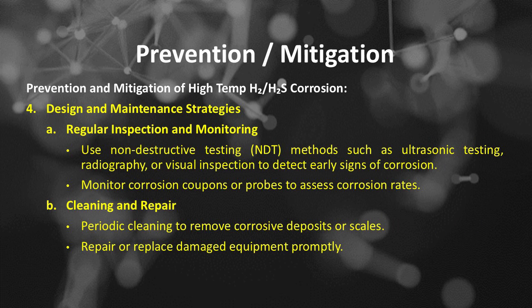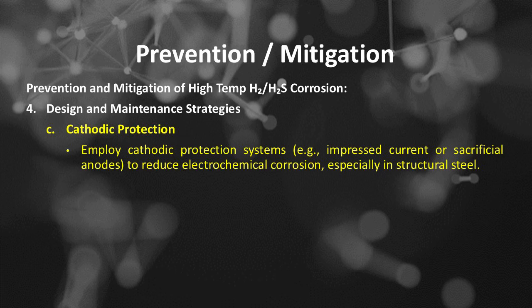Number 4 of prevention and mitigation methods is design and maintenance strategies. A: regular inspection and monitoring. Use non-destructive testing (NDT) methods such as ultrasonic testing, radiography, or visual inspection to detect early signs of corrosion, monitor corrosion coupons or probes to assess corrosion rates. Number B, cleaning and repair. Periodic cleaning to remove corrosive deposits or scales, repair or replace damaged equipment promptly. Number C, cathodic protection. Employ cathodic protection systems, such as impressed current or sacrificial anodes, to reduce electrochemical corrosion, especially in structural steel.